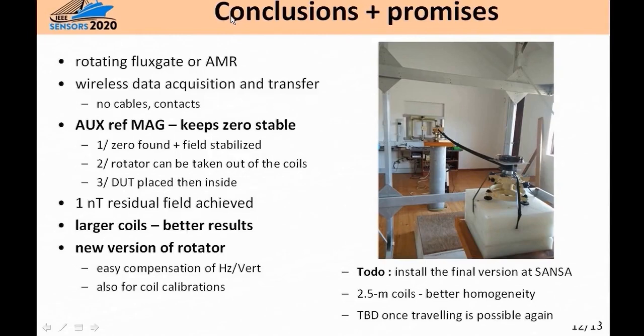So now it's time to go to conclusions and our promises for the future. We created a system with a rotating Fluxgate or AMR, with a wireless transfer and acquisition, and with the help of another magnetometer, which is auxiliary and outside of the coils, we can establish a 0 and stabilize the field. Then we can of course take the rotator out of the coils, and place a device under test in our coils, so we can calibrate in 0 fields, or we can also preset other fields very precisely. We have achieved 1 nanotesla residual field, and of course if we go to larger coils, we think we will have better results because of higher homogeneity.